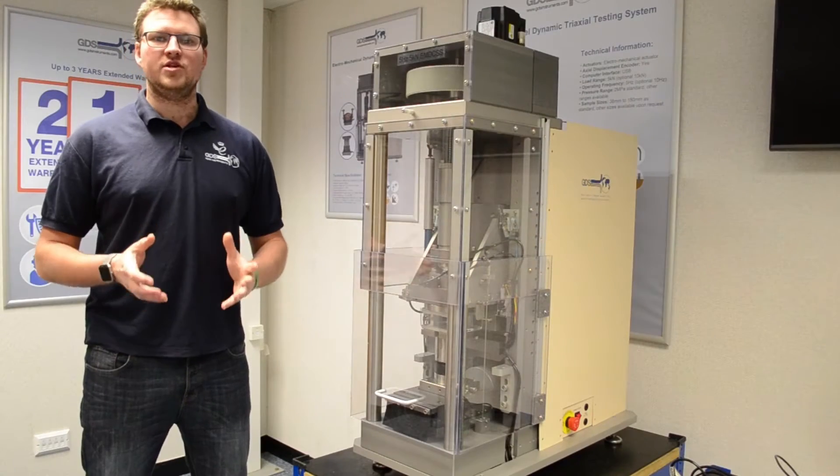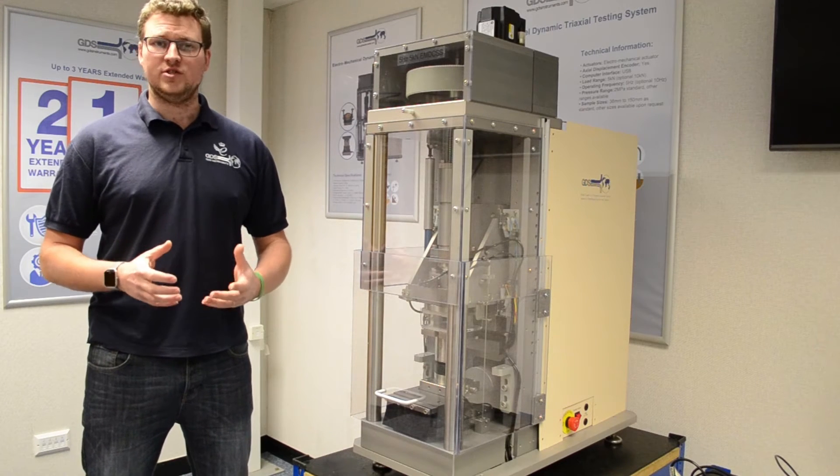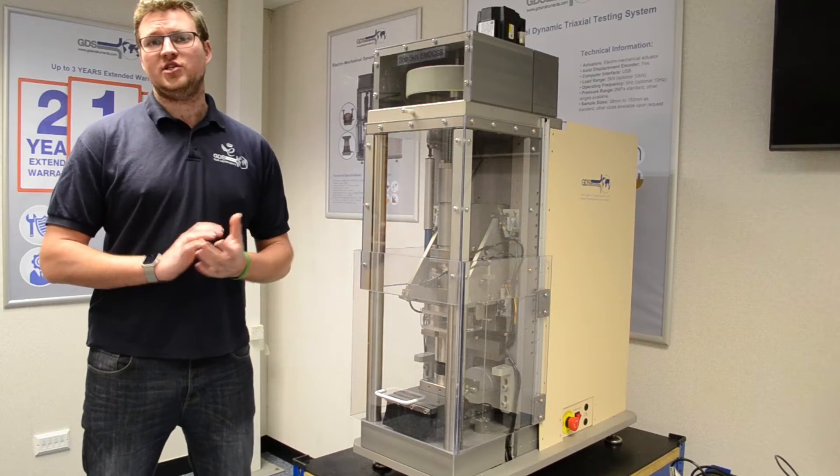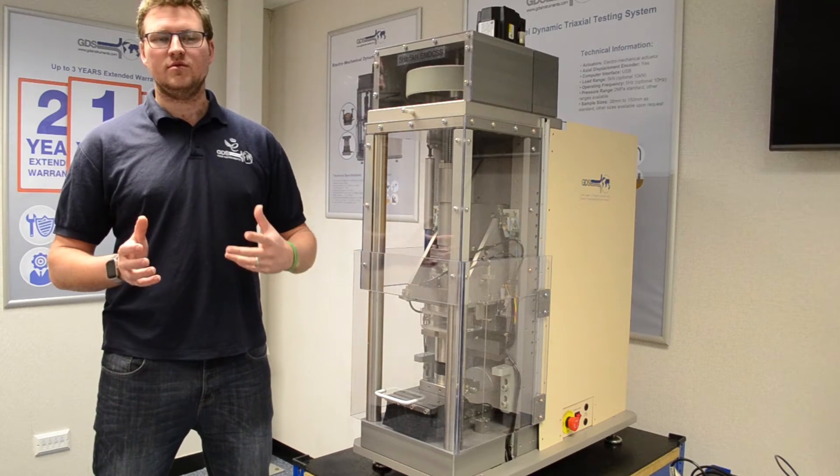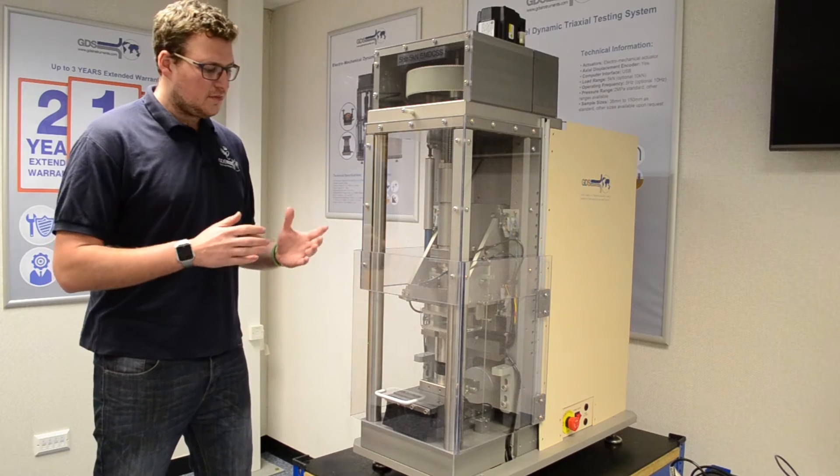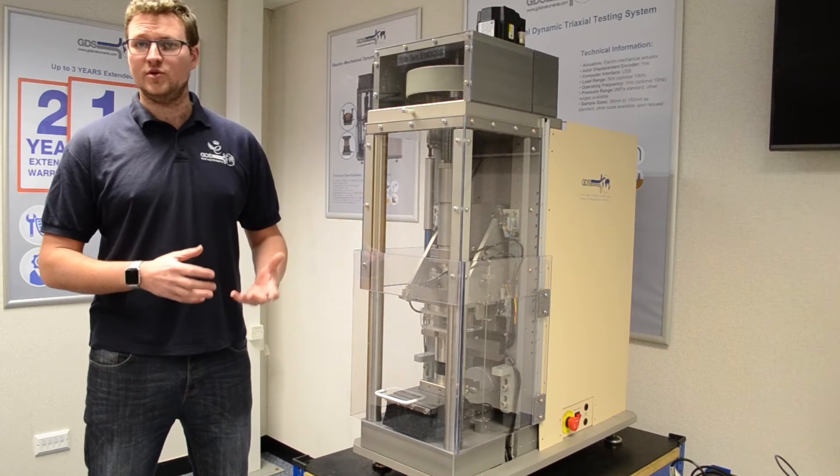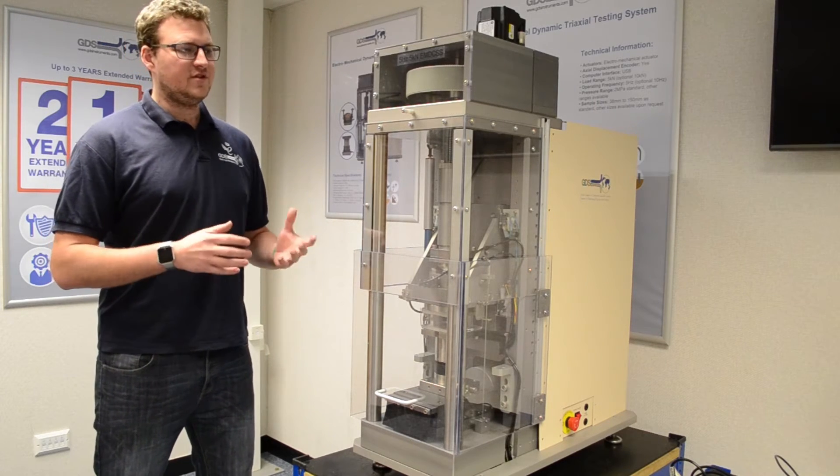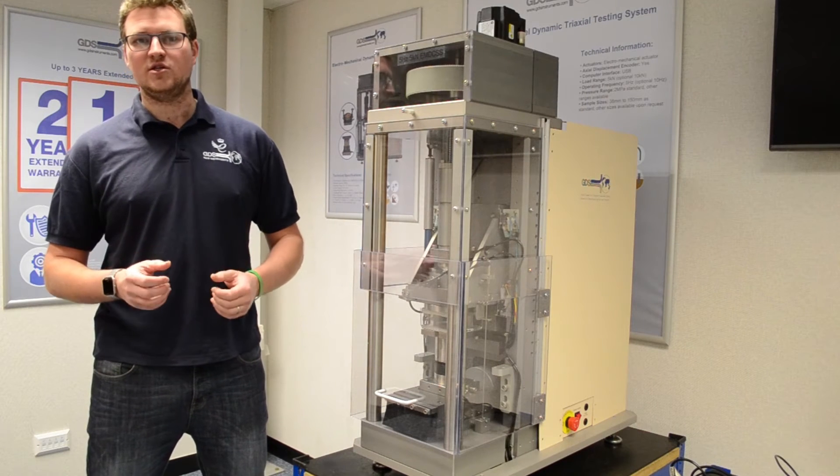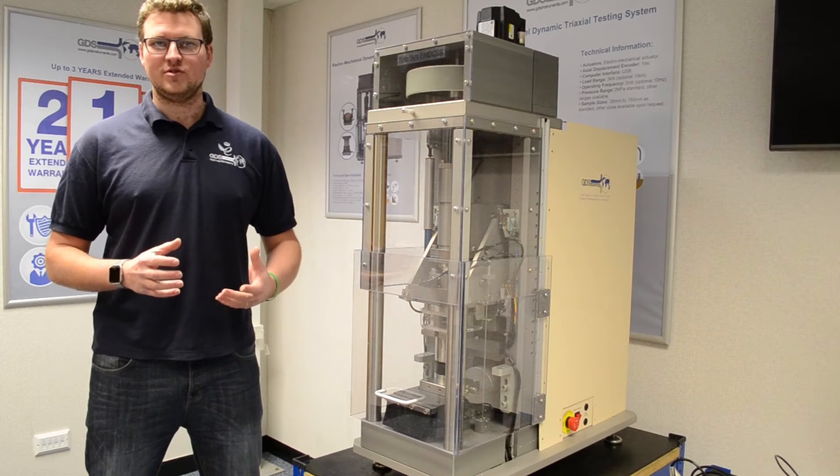One of the most important designs and features about this piece of equipment is the overall stiffness of the system. You may hear people refer to things such as system compliance and why that is quite important within your testing. Because we're trying to measure such small strains while testing samples within this machine, if the system isn't stiff enough and it starts to bend and flex and twist, we could end up measuring those system compliances within our test results, effectively ruining the results of which we're trying to achieve.